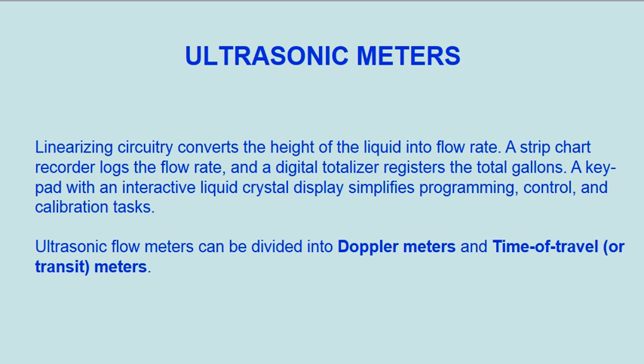Linearizing circuitry converts the height of the liquid into flow rate. A strip chart recorder logs the flow rate, and a digital totalizer registers the total gallons. A keypad with an interactive liquid crystal display simplifies programming, control, and calibration tasks.